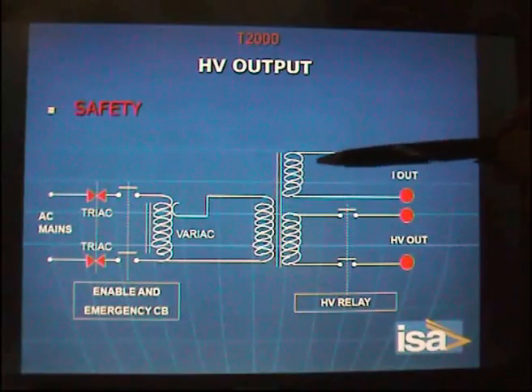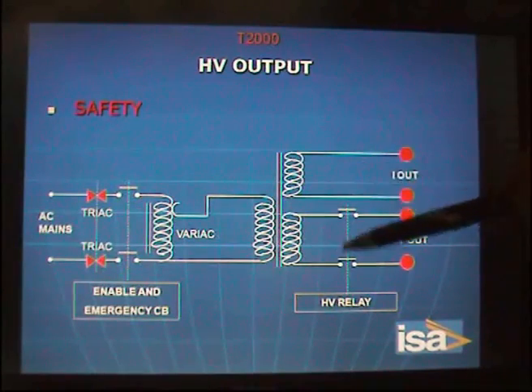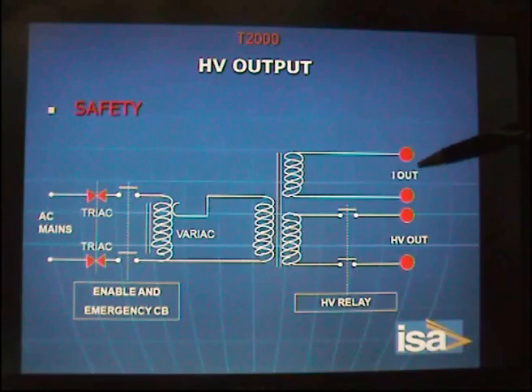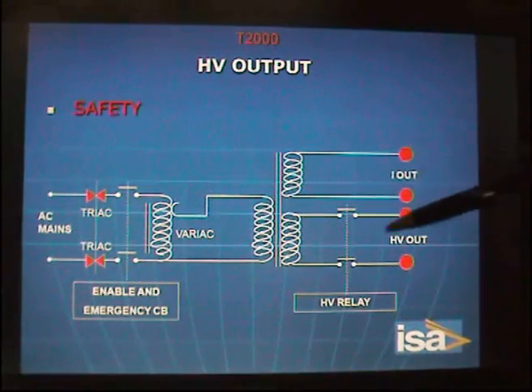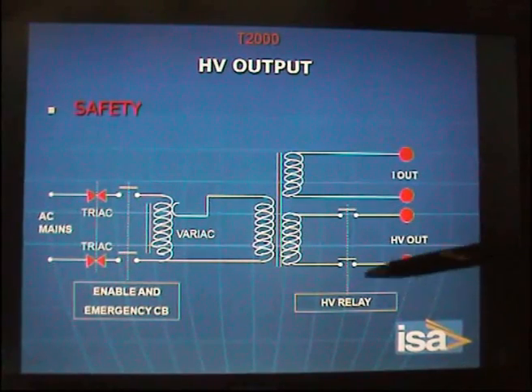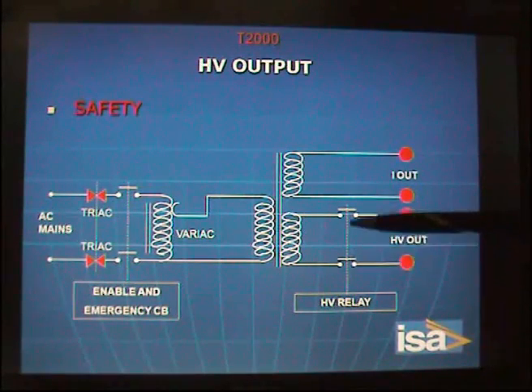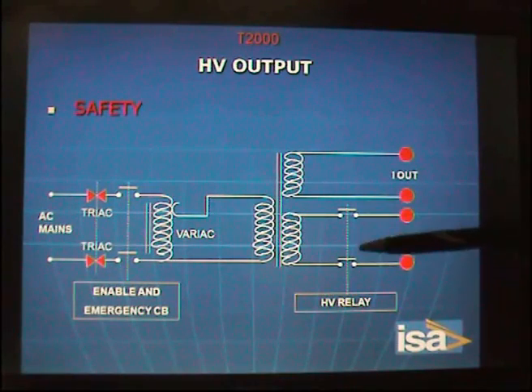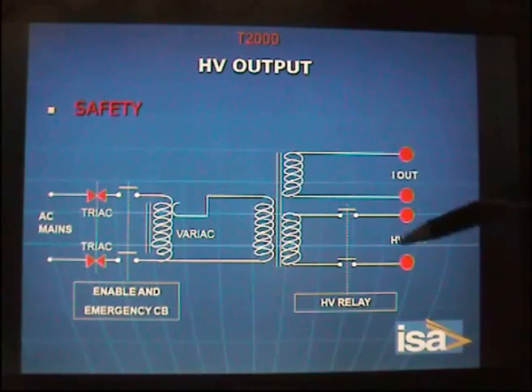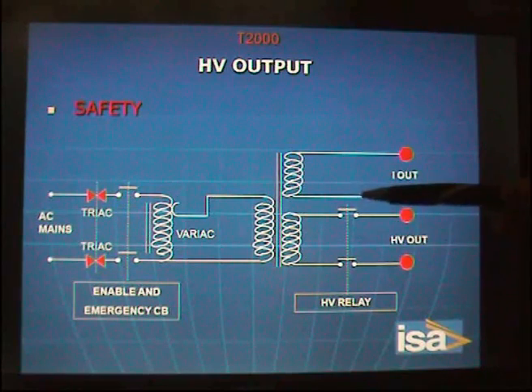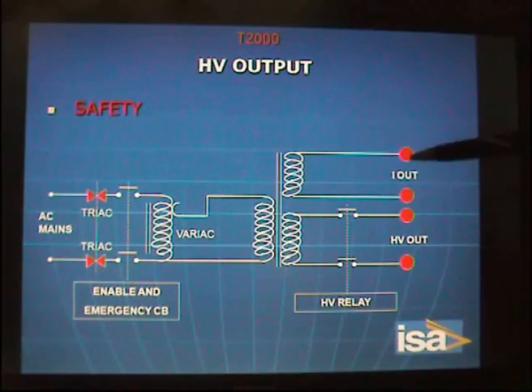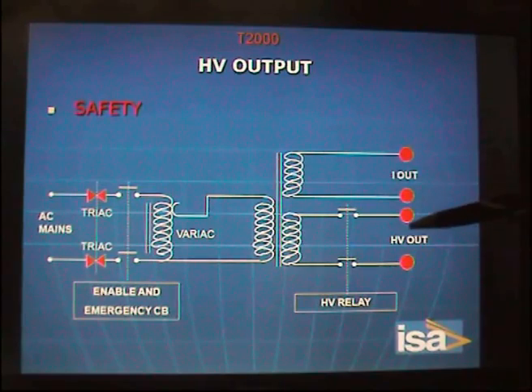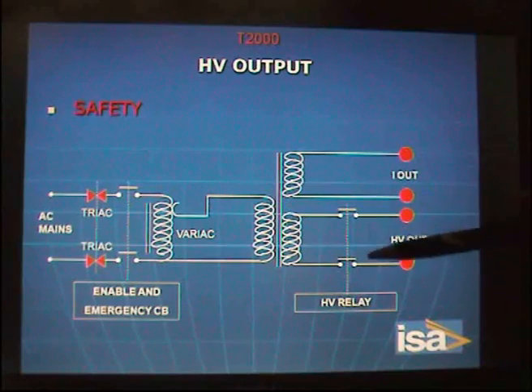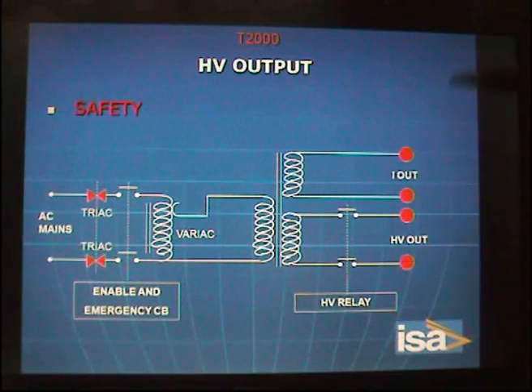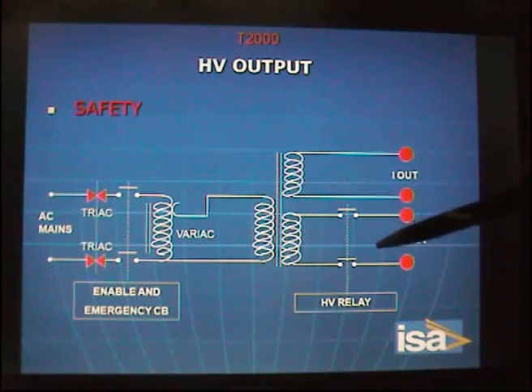The next is that, again, we have a transformer inside, with many turns on the secondary side. And these outputs here, of course, when I adjust the variac, are there, together with the output here, and this is the high voltage output. But we have a second item inside. It is the high voltage relay. This high voltage relay stays closed only when you turn the key and keep the start button pressed. Otherwise, it is immediately opened, and this is the safety that we have. So when you are not generating voltage, on the sockets you have nothing. Okay? When you are generating voltage, you also have current if there is something connected, so don't have anything else connected. As soon as you remove your finger from the start button, the output is removed.